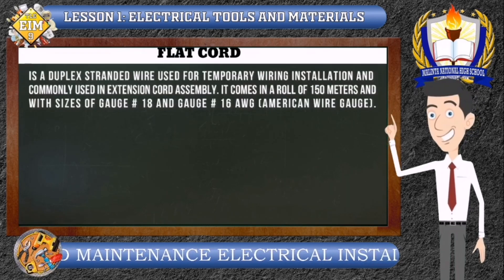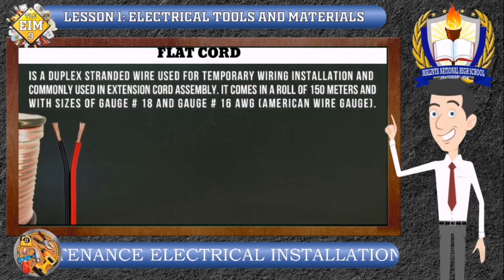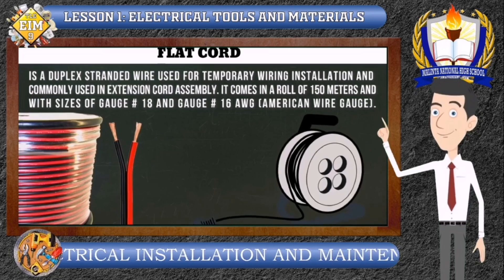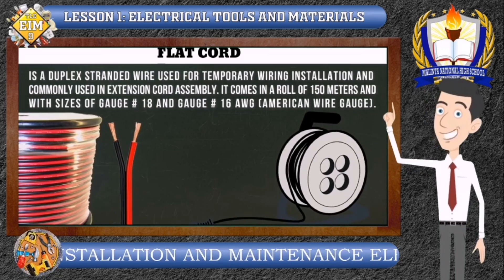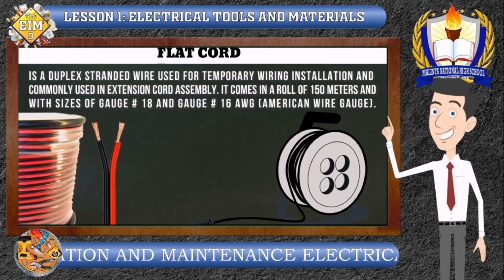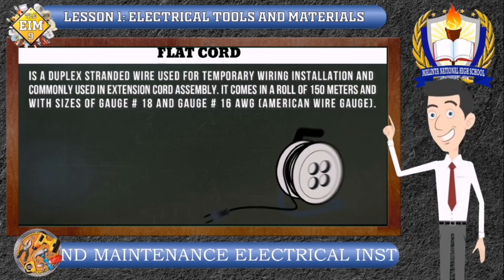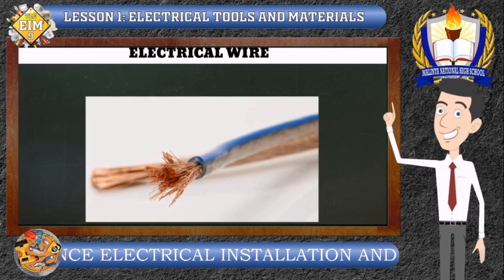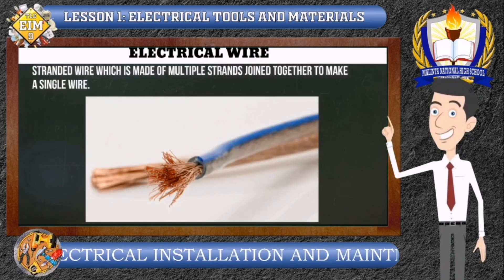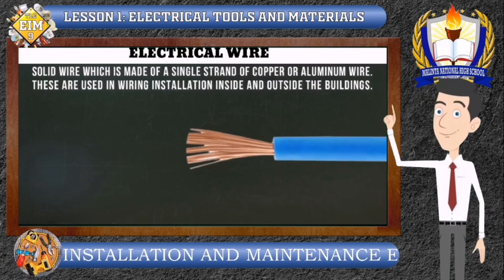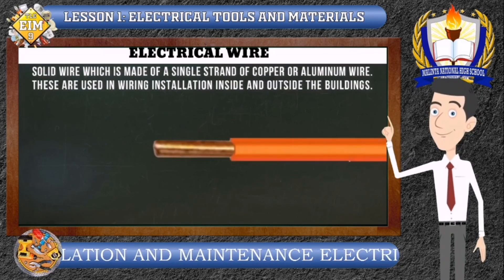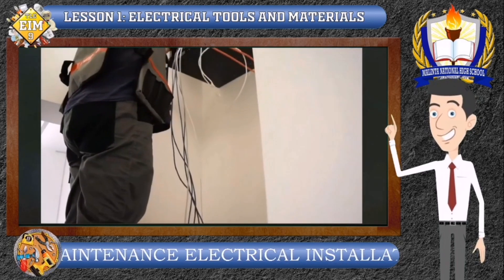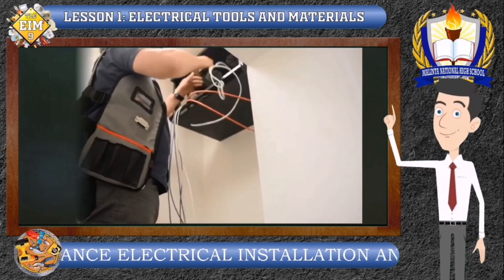Flat Cord. A flat cord is a duplex stranded wire used for temporary wiring installation and commonly used in extension cord assembly. It comes in a roll of 150 meters with sizes of gauge number 18 and gauge number 16 AWG (American Wire Gauge). Electrical Wire or Conductor. An electrical wire or conductor can be a stranded wire, made of multiple strands joined together to make a single wire, or a solid wire, made of a single strand of copper or aluminum. These are used in wiring installation inside and outside buildings.